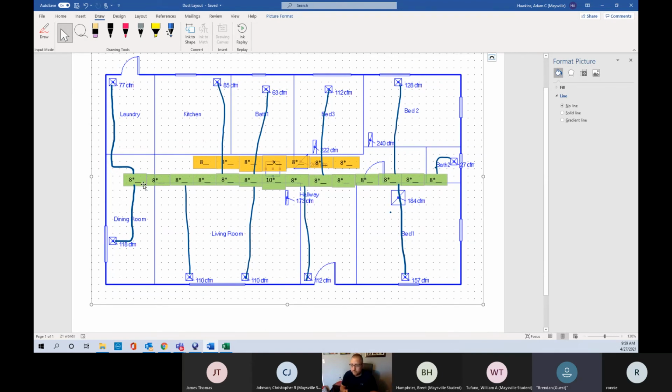On the supplies to the rooms, you want us to run round duct, correct? Yes, round duct. Now, the one thing I did want to say is flex. If you wanted to run flex, this one has a wire helix flex duct equivalent, and you can do it that way. You can say, okay, at a 0.04 at the top, at 76 metal. Let's see, am I looking at that right? 0.4 or 0.04? 0.04, sorry. 6-inch duct.